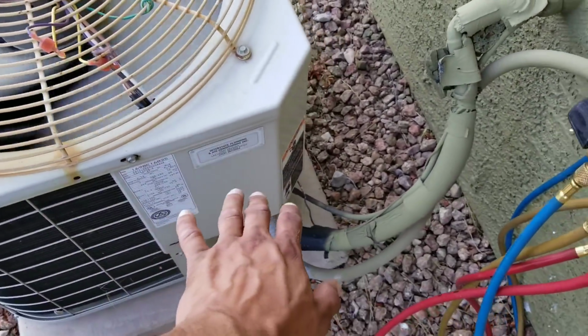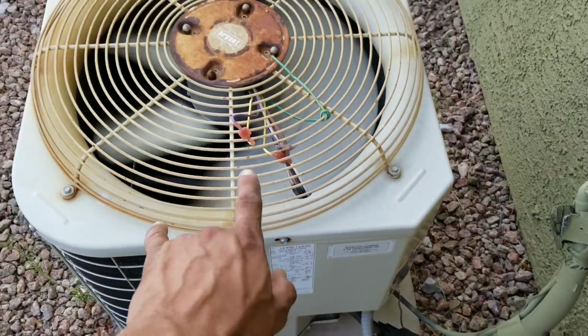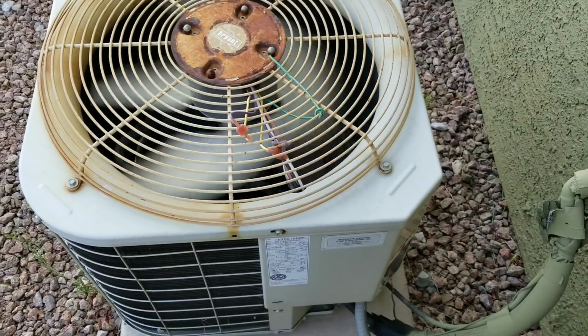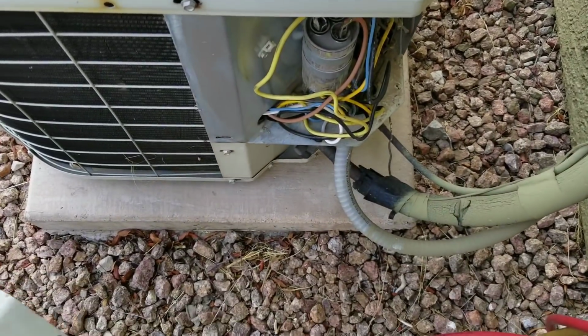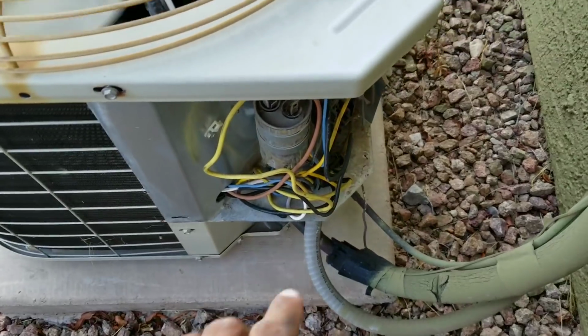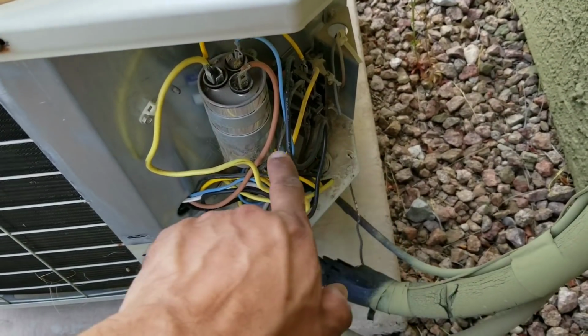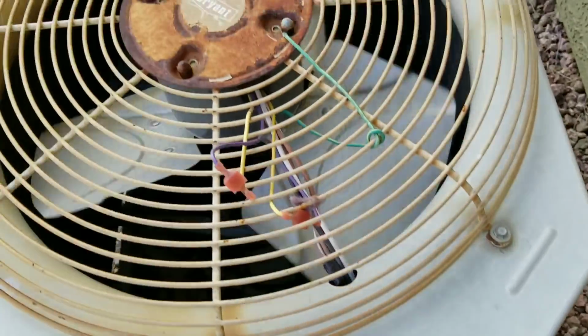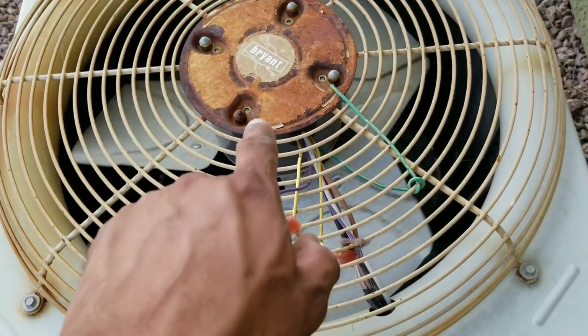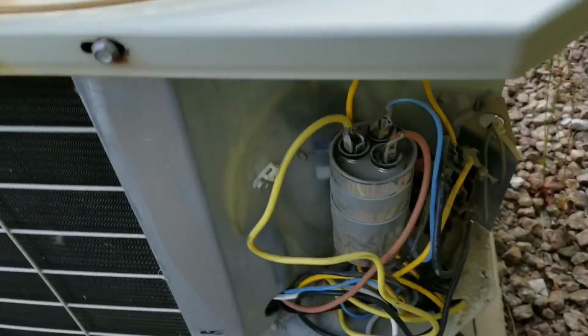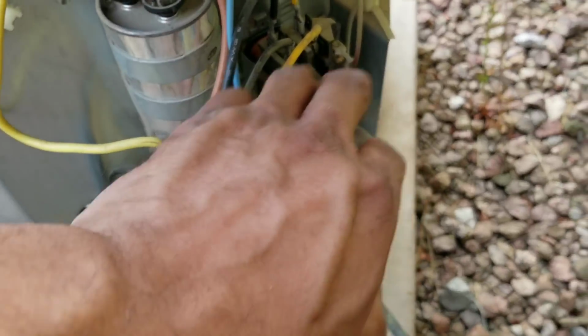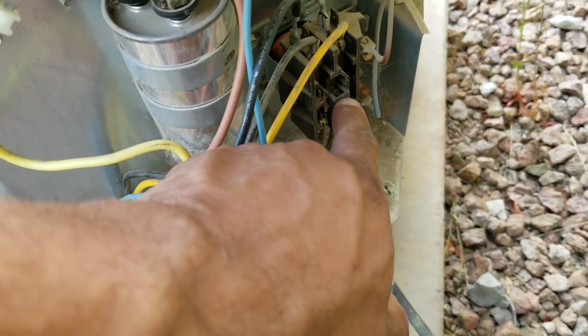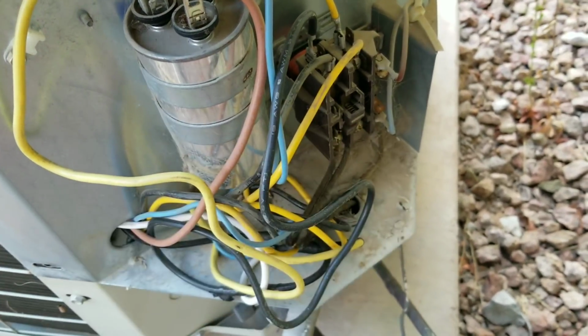I do see that I have voltage coming from my contactor because my fan motor is on. I'm going to remove my side panel, and this will give me access to my contactor and my capacitor. You can see here the fan motor just turned off. The reason that happened is because the thermostat is no longer sending a signal to my contactor to engage.